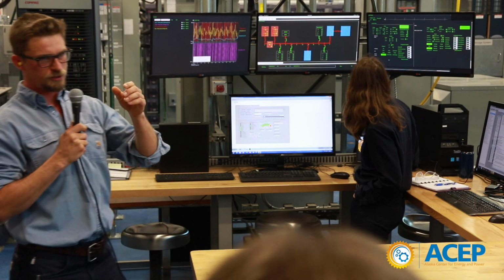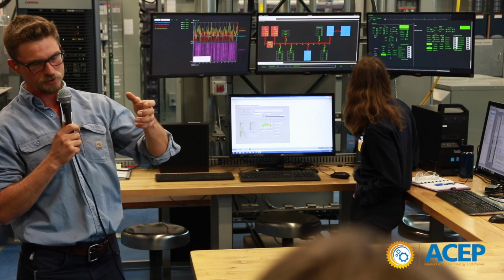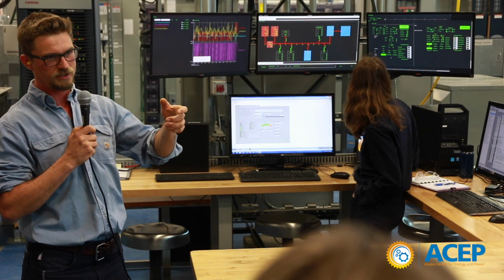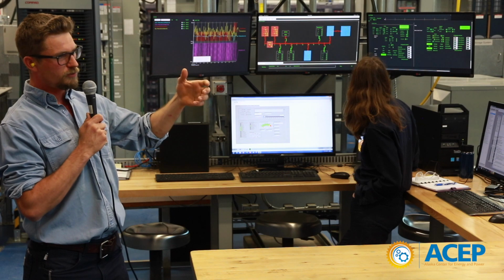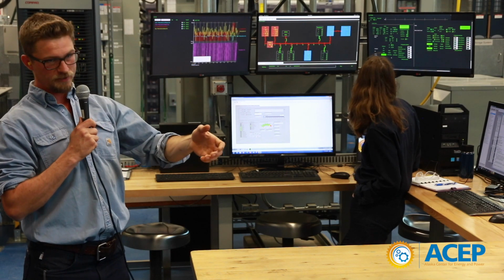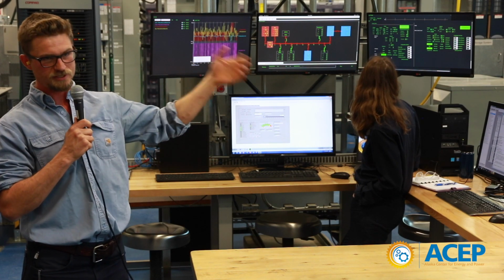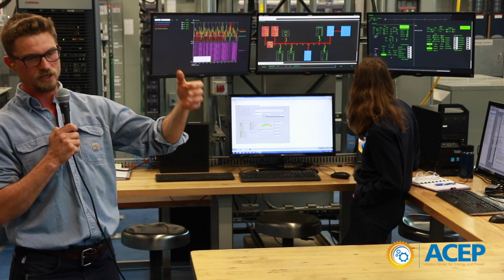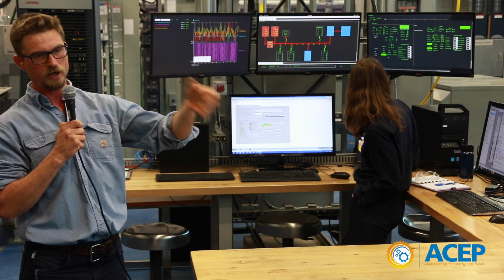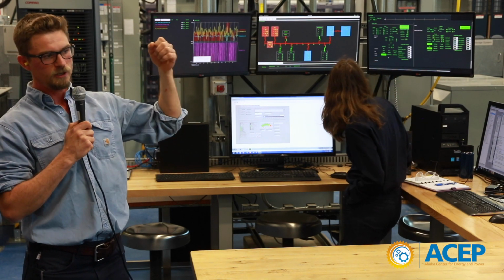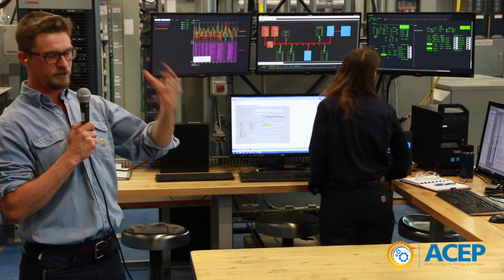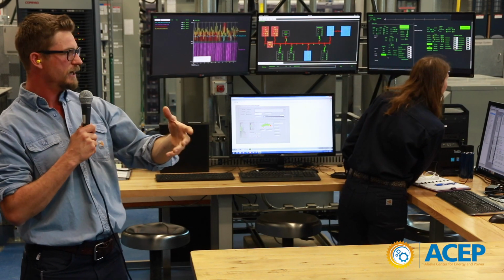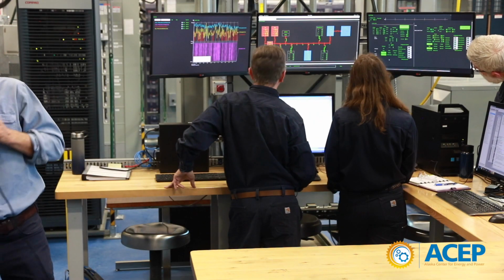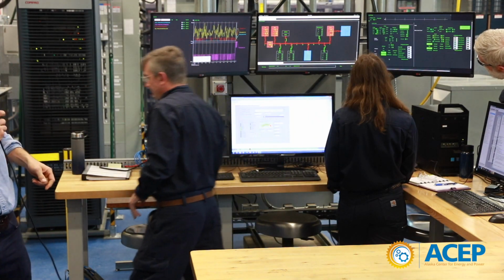So basically there's 2 circuit breakers that have to close to energize our battery system. The first one is going to close on the DC bus and connect our DC bus to our inverter. The second one is going to close the inverter onto the AC bus. So the second one to close needs to synchronize first, right? So everything needs to synchronize with the grid. But they're working on something like that. Alright, so that's the first bang.